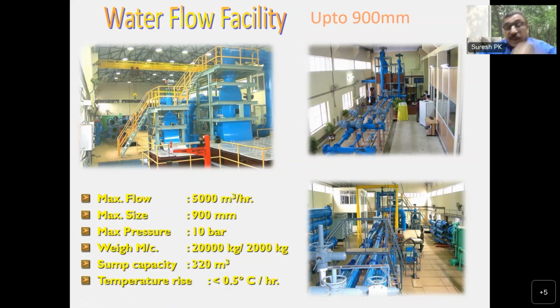The point at which you start the measurement is known. And when the weighing tank is full, you divert it back. Then you know the time for which the collection is made. You know what is the total collection in the weighing tank. And then it becomes very simple. What is the indication of the meter? You know the meter reading, you know the total volume collected, and at what flow rate it is collected. And then the weighing machine.